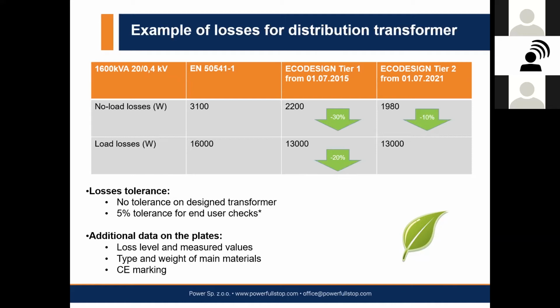The new regulation was divided into steps, Tier 1 and Tier 2. Tier 1 is already working. We are supplying all distribution transformers inside the European Union according to Tier 1. And for 2 years we have already been supplying Tier 2 transformers too, requested mostly in Germany but also in Scandinavian markets, which are very sensitive to ecological problems. So they save money, but they also prefer to buy a more ecological transformer. Next year, starting from the 1st of July 2021, we have step 2. So eco-design Tier 2 is entering into force.